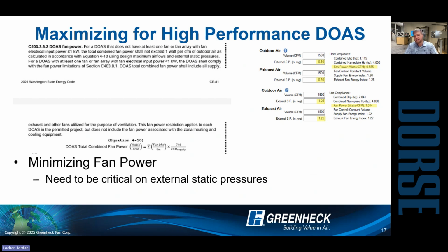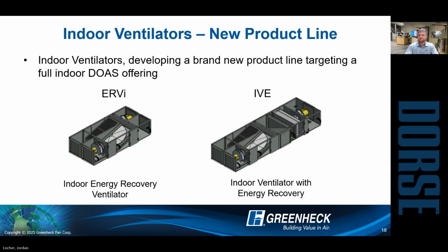Most critical thing we see here is really doing a good job with those external pressures, right? So, how much ductwork is there? What is this unit ventilating into? We do see a lot of times where maybe folks are just kind of guessing at those numbers. Being more exact is going to really help drive down that watt per CFM number and make sure we have an accurate assessment of that. The other thing too is, the less restriction on the unit, obviously the less fan power we're going to need. Okay, so those are ways to maximize the use of ERVs.